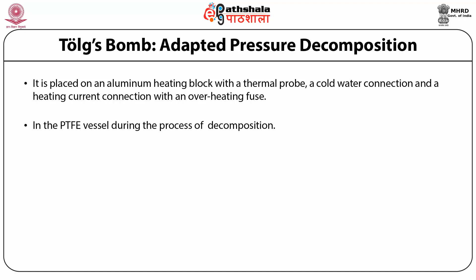It gets shut off. In the PTFE vessel, during the process of decomposition, the temperature limit is about 170 degrees centigrade and the sample must contain 100 milligrams of carbon per 35 ml vessel. A high pressure asher was more recently presented by Knapp, which performs decomposition at 180 to 300 degrees centigrade, practically generating a carbon-free solution. This was done to overcome the limitation of the Tölg bomb. The scheme of Knapp's high pressure asher for sample preparation is shown here.